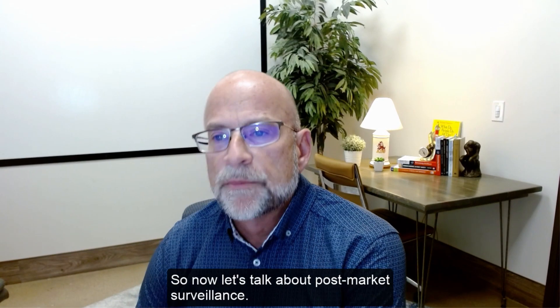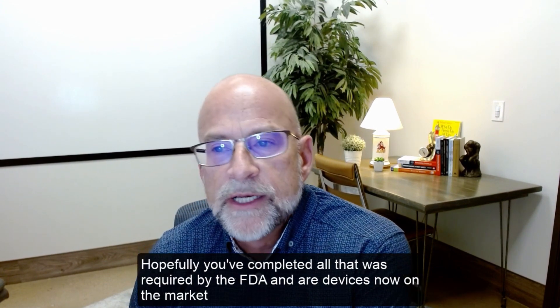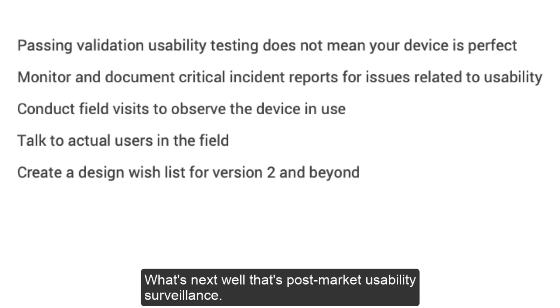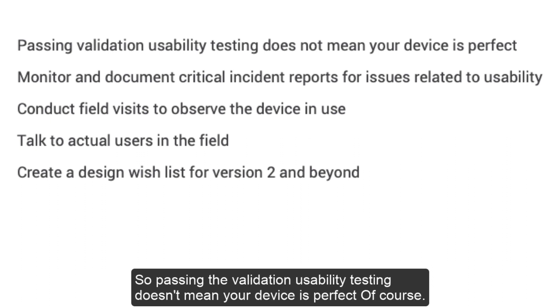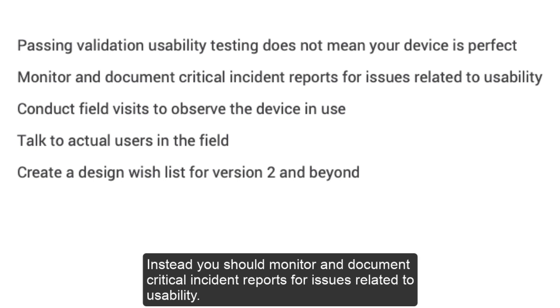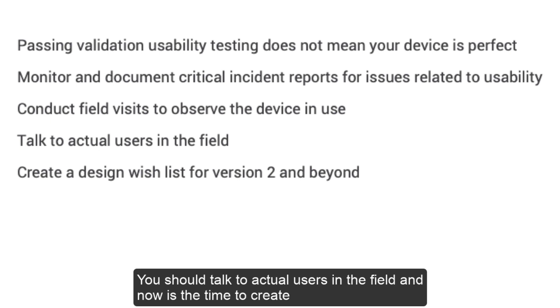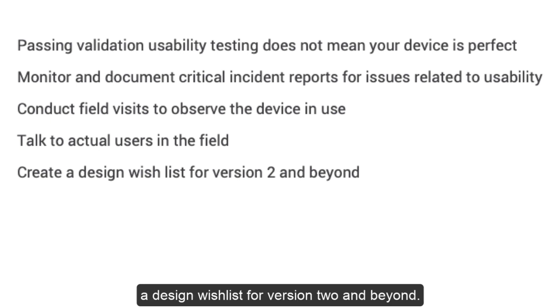Now let's talk about post-market surveillance. Hopefully you've completed all that was required by the FDA and your device is on the market — what's next? That's post-market usability surveillance. Passing the validation usability testing doesn't mean your device is perfect. You should monitor and document critical incident reports for usability issues, conduct field visits to observe the device in use, talk to actual users in the field, and now is the time to create a design wish list for version 2 and beyond.